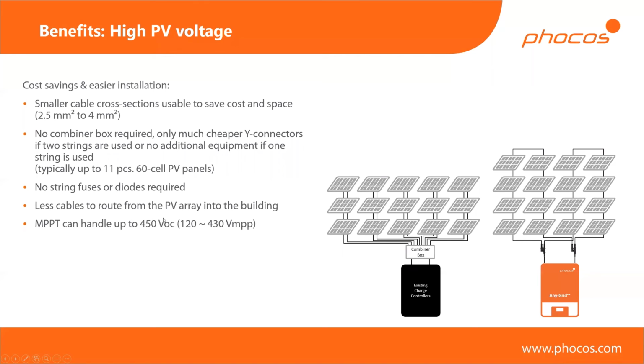I've mentioned that. You generally have a lot less cables coming into your building, because if you're working with this traditional setup, either you have, in this case, 5 pairs, so 10 cables running into your home. So that's a big hole to drill to the outside world. Or you have your combiner box outside and bring in just the common positive and negative, in which case you still have thicker cables than for the AnyGrid. And on top of that, your combiner box now needs to be waterproof, UV proof, etc., because it's sitting outside. So those are the trade-offs you would have with the combiner box. You don't have any of that with the AnyGrid.